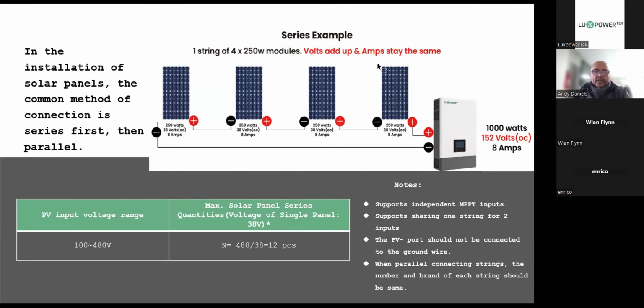Okay. So in a case like this, our MPPT supports 2 independent inputs, and we went through that previously. We spoke about each one can do 4,000. We do sometimes get calls asking, is it 4,000 total or 4,000 for the 2? In the case of the independents, it's 4,000 watts per input. You've got to stay under 380 volts, and you've also got to stay under 17 amps.